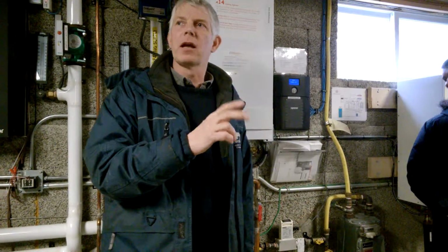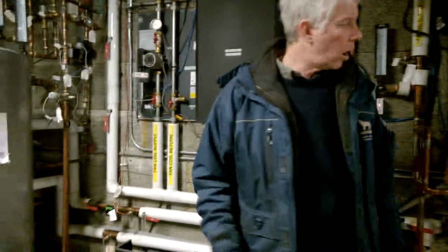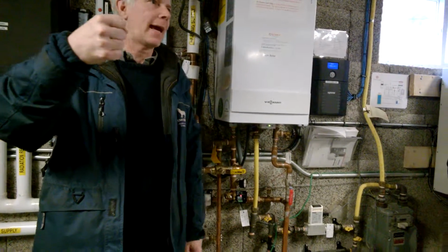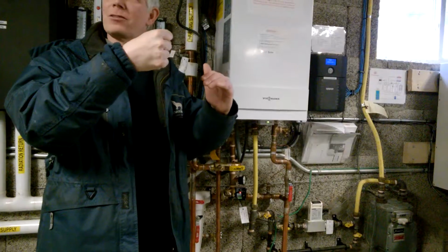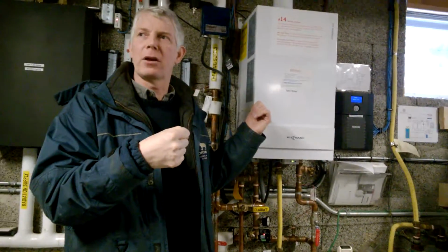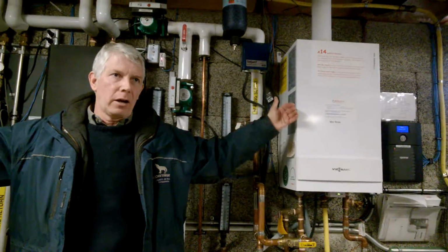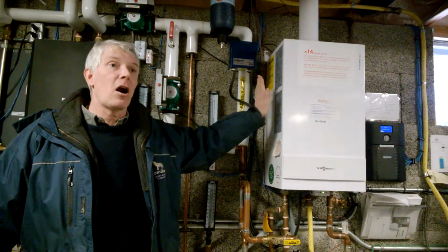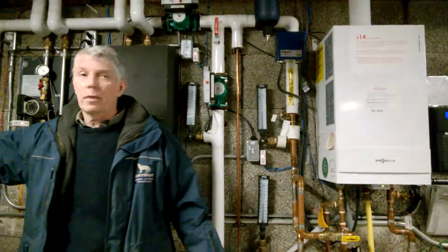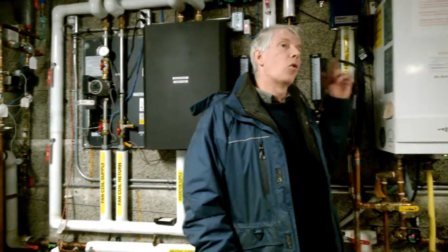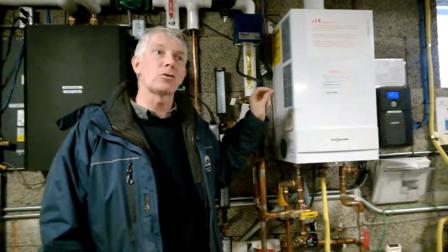Okay, so you hear of instantaneous hot water heaters, they bring the domestic water through the boiler. Well, what happens in a kettle when you heat water? You get the calcification in the bottom. The same thing happens in those. When we put this intermediary hydronic loop between the very hot surface of the flame and the domestic water that has all the minerals in it, I don't get the calcification at either end. At this end, the water that's in that loop is closed. It's very clean water, a little bit of minerals come out of it, and then they're done. That's all the minerals that there were.